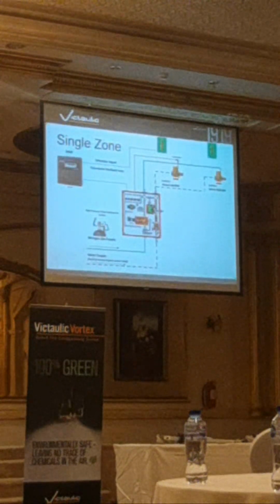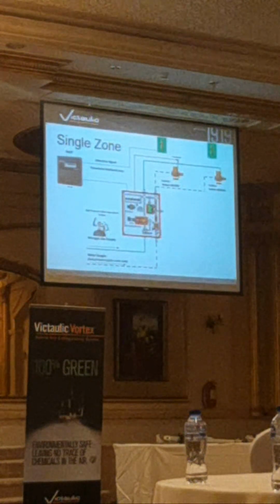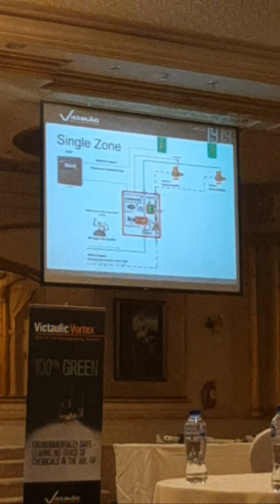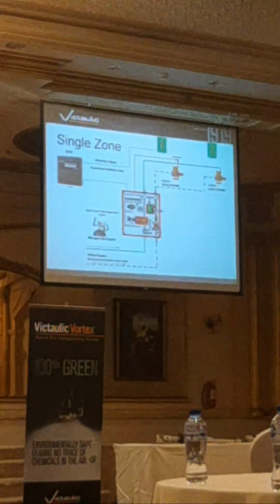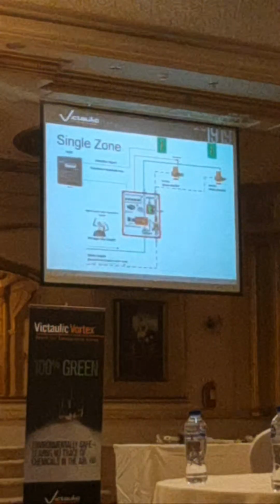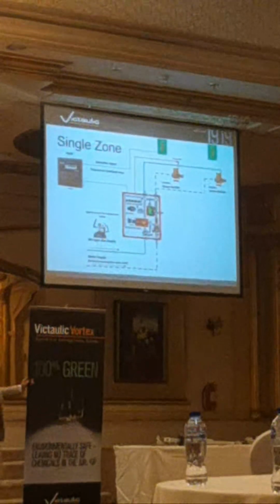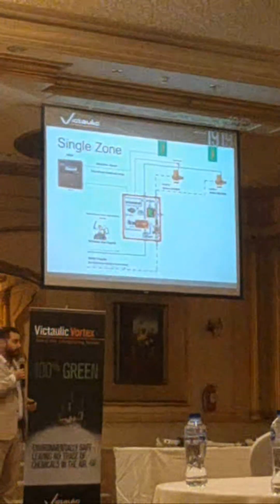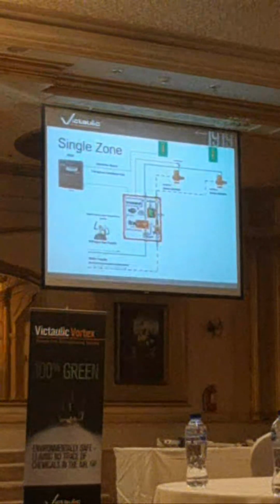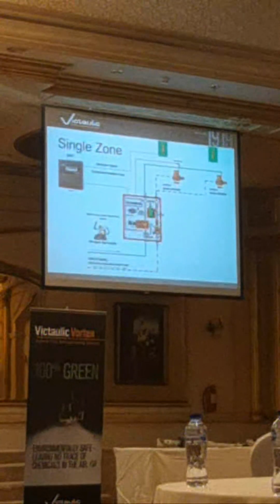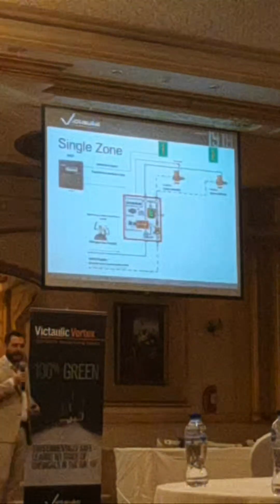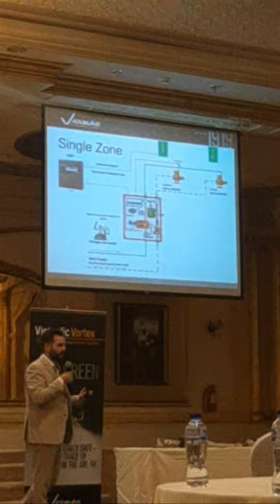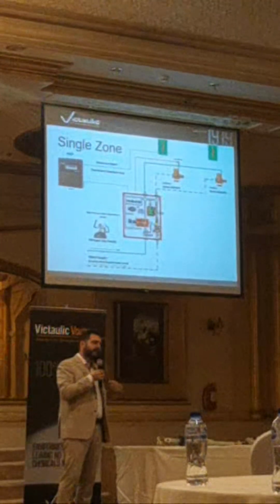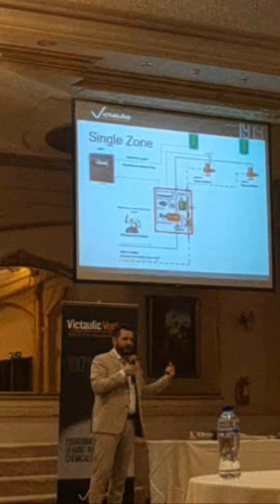The pipe material to be used there, on the nitrogen, that's going to be your standard normal pipe. All the pipe work after your panel will be dry at all times, and that is the reason, but the pipe work before will be under pressure up until the panel, so that's the reason why you need to have corrosion protection, and you cannot use just carbon steel, to avoid that any debris is going to the nozzles. Okay?